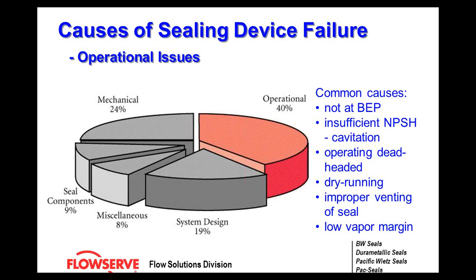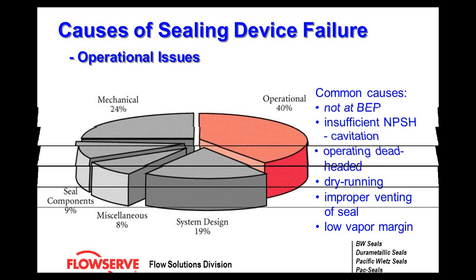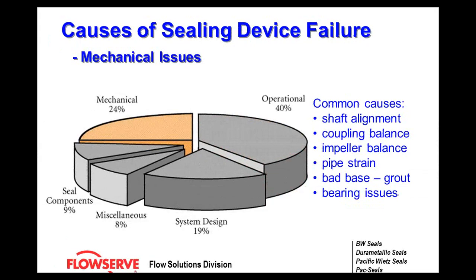Low vapor margin: these are flashing fluids. Generally hot hydrocarbons will flash at atmospheric conditions, so as the fluid film passes across the mechanical seal it can flash on the atmospheric side and cause a failure. Another common example would be boiler feed situations where you have hot water at 250 or 280 degrees, which will also give you a flashing situation.